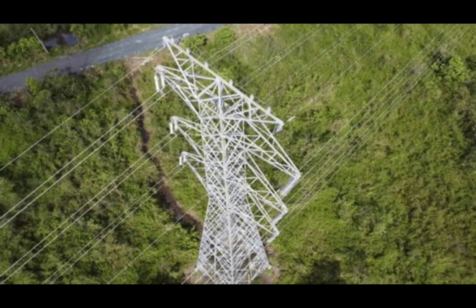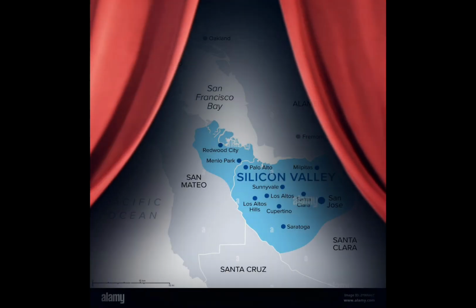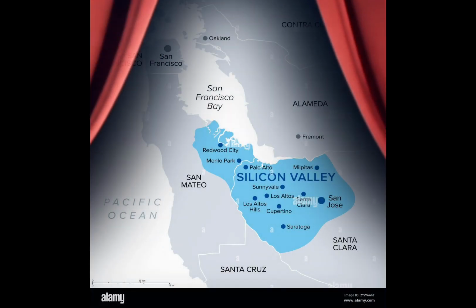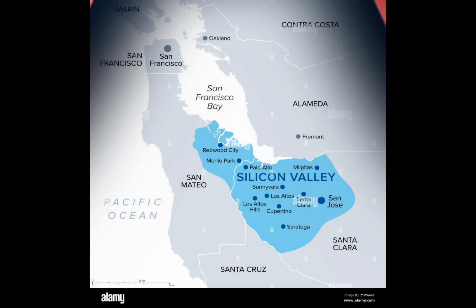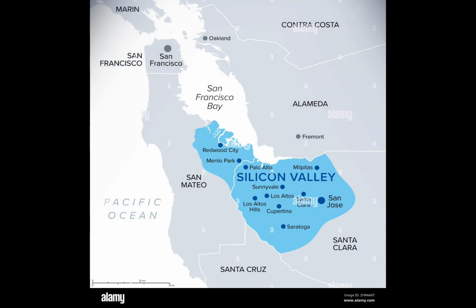As thousands of gallons of insulating oil bled out onto the gravel, the transformers overheated and began to shut down. Silicon Valley, the technological heart of the United States, was pushed to the absolute brink of a catastrophic blackout. The local utility, PG&E, had to frantically reroute power at the macro grid level just to keep the lights on. It took 27 days to repair the damage.